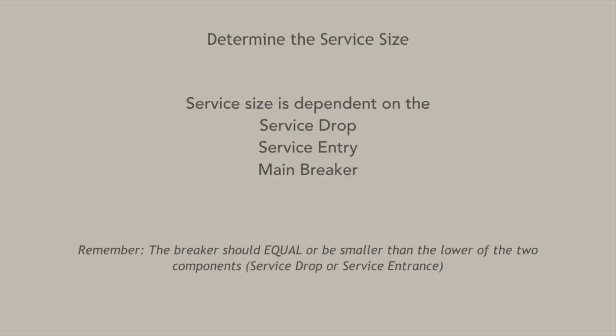To determine the service size, you must determine which component has the lowest rating: the service drop, service entrance, or main breaker. For example, if the service drop is a 200 amp rated wire, the service entrance is a 150 amp rated wire, and the main breaker is a 100 amp breaker, then the service size of this house would be 100 amps. If the house had a main breaker of 200 amps in this example, then the service size would be 150 amps. This would be reported as a defect, because the 150 amp service entrance cable would be overloaded before it tripped the main breaker, which is too big to protect the smaller cables. The breaker is the defect, not the wire.